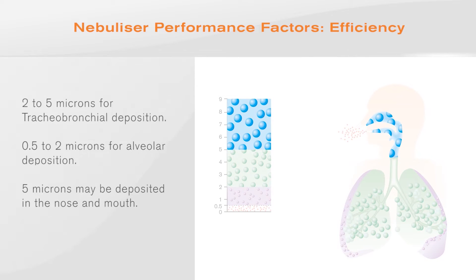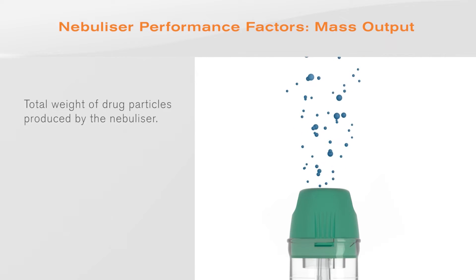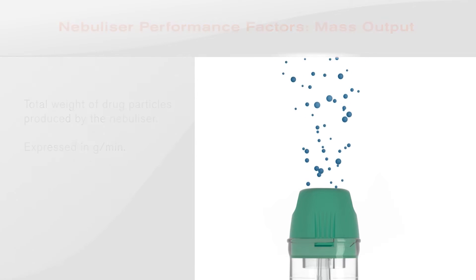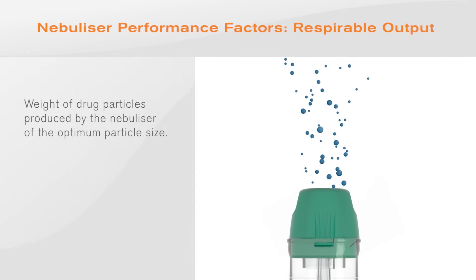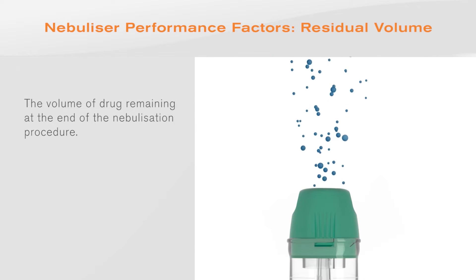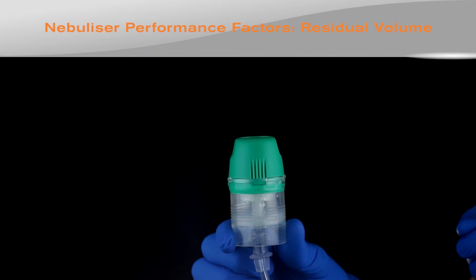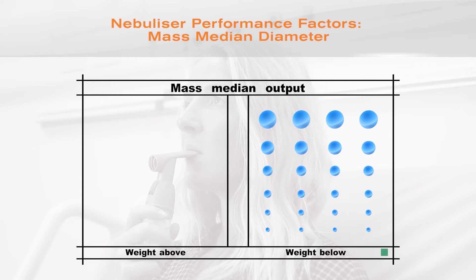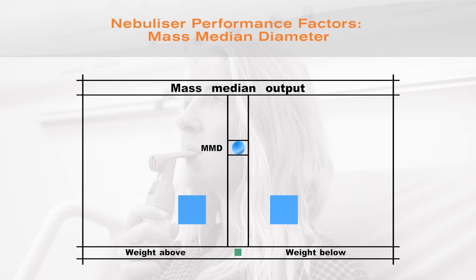Particles larger than 5 microns may be deposited in the nose and mouth, resulting in the drug being swallowed. Mass output is defined as the total weight of drug particles produced by the nebuliser, expressed in grams per minute. Respirable output is the weight of optimum-sized drug particles produced, also expressed in grams per minute. Residual volume is the volume of drug remaining at the end of nebulisation, which may be minimised by tapping the cup when the nebuliser begins to splutter. The mass median diameter (MMD) is defined as the point where half the mass of nebulised aerosol is in droplets larger than the MMD and the other half are smaller.